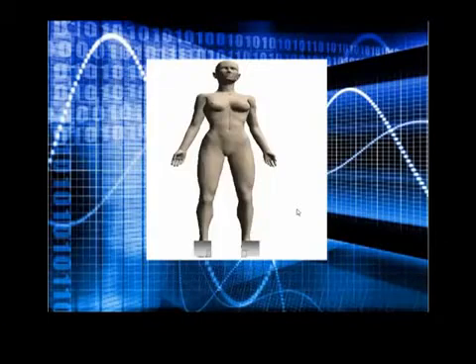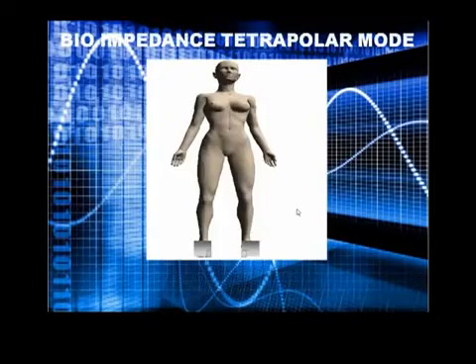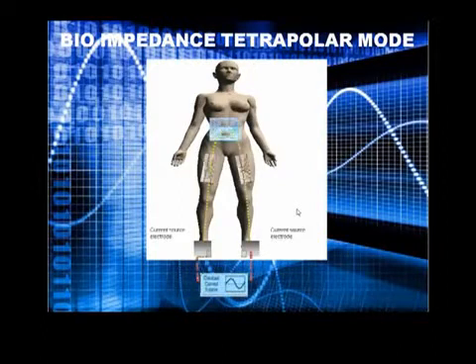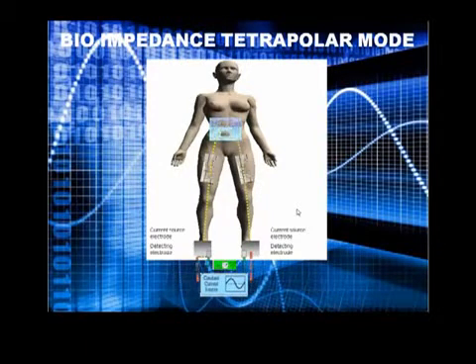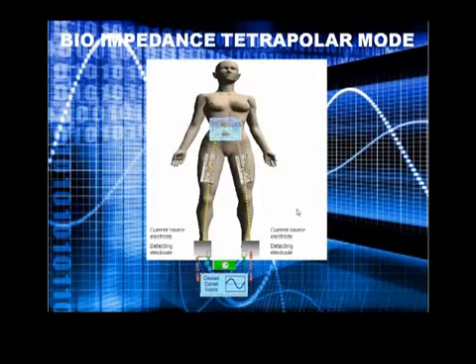Signal processing analysis for the bioimpedance in tetrapolar mode uses a mono frequency of 50 kHz, following the sending of weak intensity through active tactile electrodes. The sensor measures the resistance and reactance between two other passive tactile electrodes and provides estimated body composition parameters from peer-reviewed algorithms.